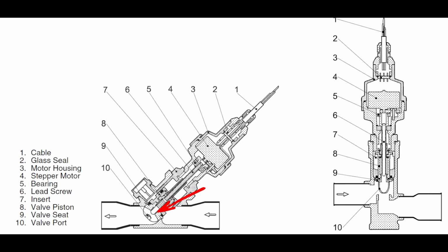These valves will first go through a closing calibration. What that means is that the controller will send a closing signal, or rather, it'll rotate the stator to close the valve fully, and it will try to seat the valve. And this is where you get this loud ticking noise that you'll hear from valves sometimes. What that is, is that it's fully rotated closed.